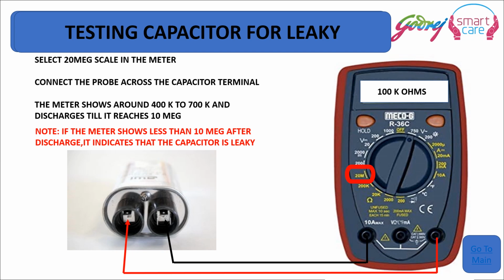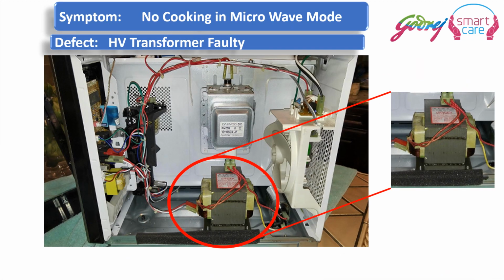If the capacitor is leaky, then it will show less than 10 mega ohms after discharge. Initially it will show 400 to 700 kilo ohms, and then after a few seconds it will not show 10 mega ohms, it will show a small value of resistance, less than 10 kilo ohms. Then we know that this capacitor is working, but it is not working to its full capacity and it is leaky. So a leaky capacitor is also equally bad and it should be replaced.